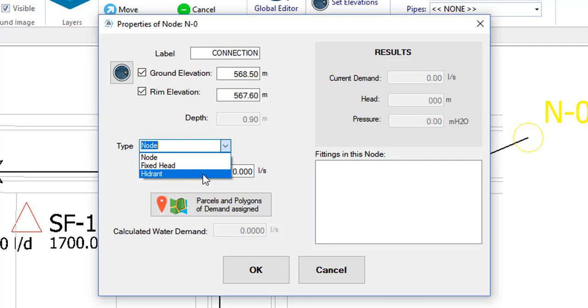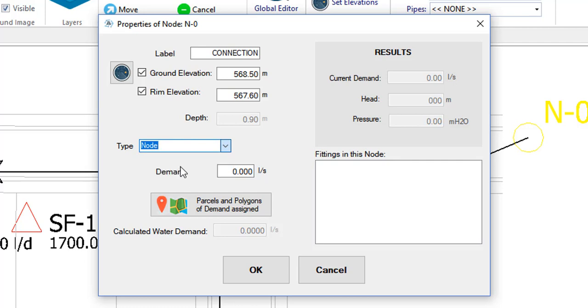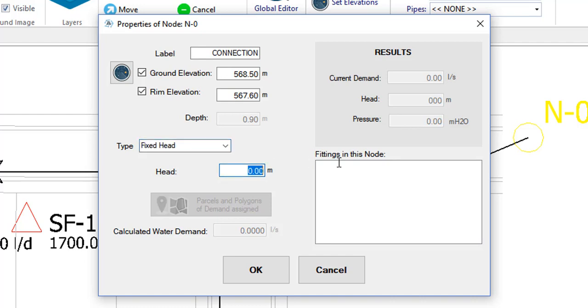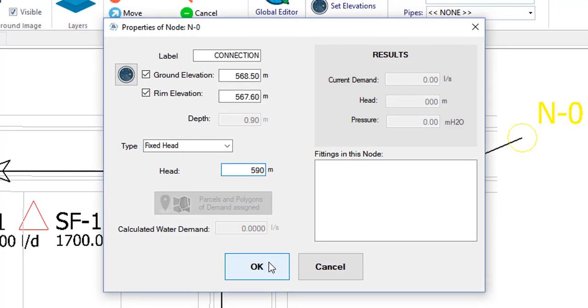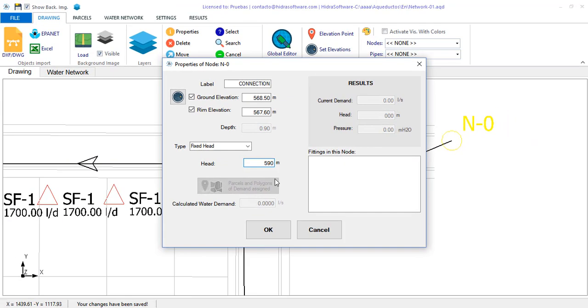This we will see in detail in another video in this series. So, in this case, we will change the node type to fixed head, entering the corresponding piezometric head value here. Keep in mind that this fixed head node can, in real terms, be any element, such as a tank, reservoir, and even a pumping station. The important thing is that, for any of these elements, you are able to extract from it the operating piezometric head for the design condition of the system.